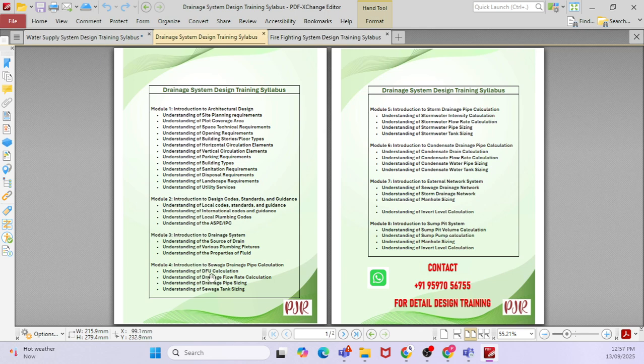Here you do DFU calculation, drainage fixture unit calculation, and how to calculate drainage flow rate, drainage pipe sizing, and sewage tank sizing, and storm drain pipe sizing. Storm drain is nothing but rainwater—how to calculate rainwater intensity, rainwater flow pipe sizing, flow rate calculation, rainwater pipe sizing, rainwater tank sizing, then understanding of condensate drainage pipe calculations: condensate flow rate calculation, condensate water pipe sizing, condensate water tank sizing.